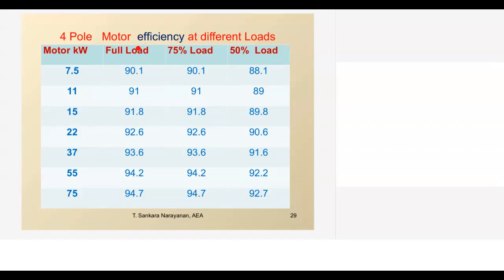So this is one advantage of high efficiency motors. Even when we are operating at low load, the drop in efficiency is very small. Again, when we go for a higher capacity rating, the drop is the same. So most high efficiency drives have an efficiency drop of 2% at 50% load. Between 75 and 100% load, there is no efficiency drop.